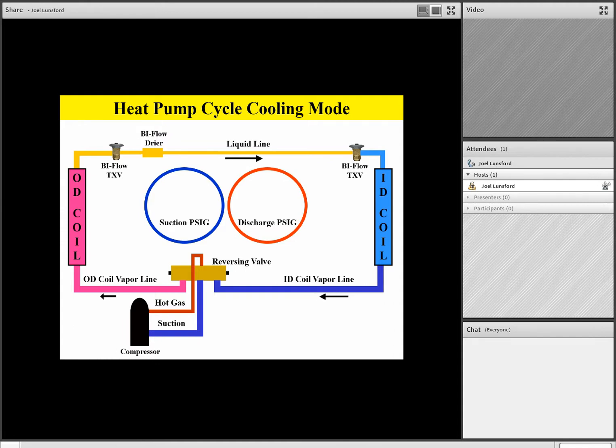So again, we take that hot gas from the compressor to the outdoor coil in the cooling mode of operation, and we condense that hot gas into a liquid. We then pass that liquid through a biflow metering device, a TXV in this case. We then pass it down through a biflow filter dryer and then down the liquid line. You'll notice there are arrows around the refrigeration circuit indicating the flow of the refrigerant. So we see liquid is flowing from left to right in this example, from the outdoor coil to the indoor coil in the cooling mode of operation.